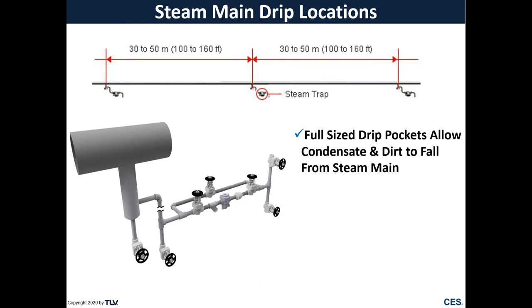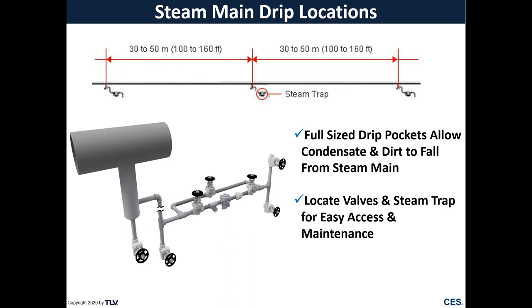And here we're going to want to have a full-size pocket to allow condensate and dirt to fall out of that steam system to be drained, so we're not carrying it downstream, degrading the quality of our steam. And it's also ideal to locate those valves and that steam trap down low, preferably near grade or somewhere where we have easy access so we can maintain that trap. We definitely don't want to have that steam trap up in the pipe rack where it's inaccessible and unmaintainable.